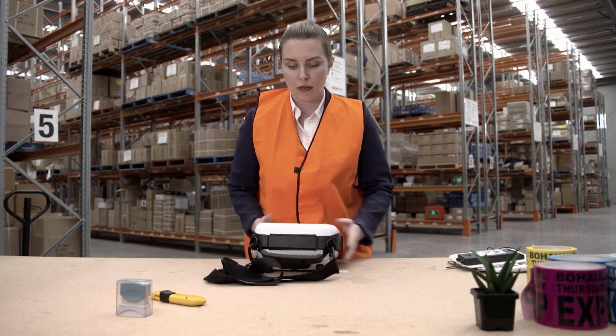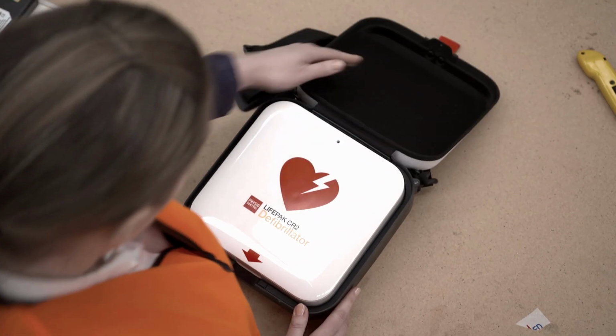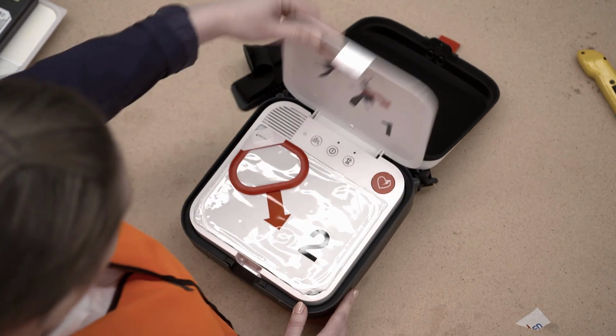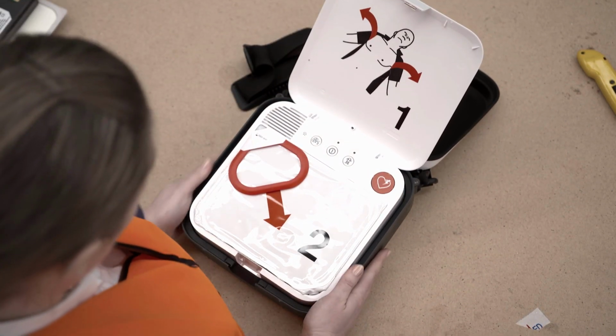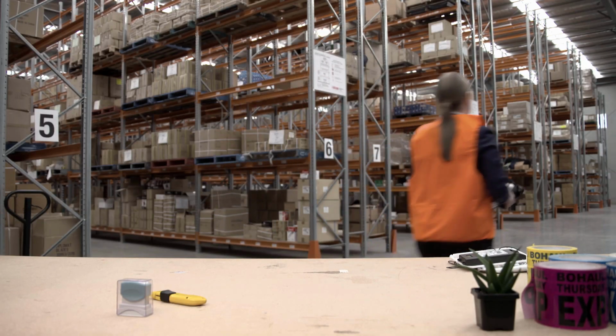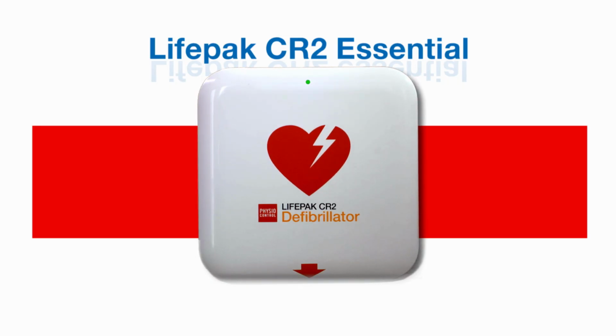Allow up to 2 minutes for the defibrillator to self-test. Open the lid to ensure the device is working correctly and then place back in your defibrillator cabinet. To ensure your defibrillator is working, once a month, simply check the light is flashing and you can rest easy knowing your device is ready to go in an emergency.